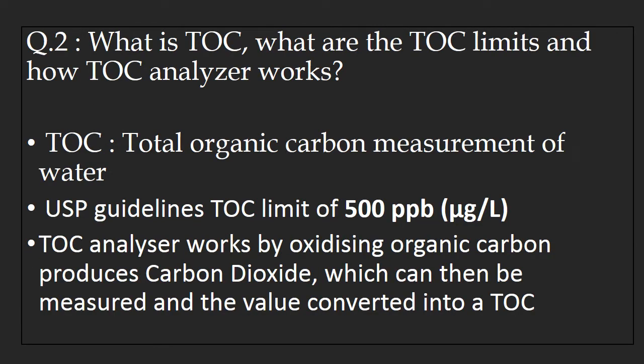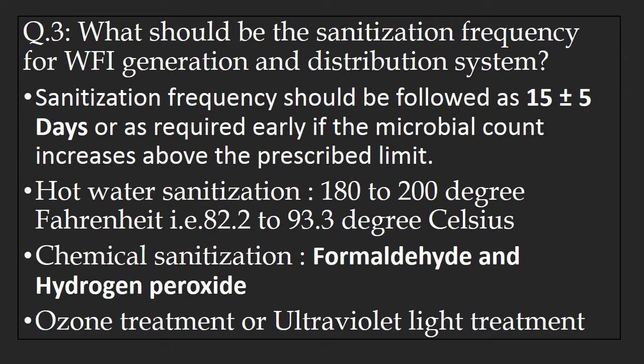Question number 2 is about TOC, that is Total Organic Carbon. The question might be: What is TOC, what are the TOC limits, and how does a TOC analyzer work? TOC is a measurement of total organic carbon in water. USP guidelines set the TOC limit at 500 ppb or microgram per liter. A TOC analyzer works by oxidizing organic carbon to produce carbon dioxide, which is then measured and converted into the TOC value.